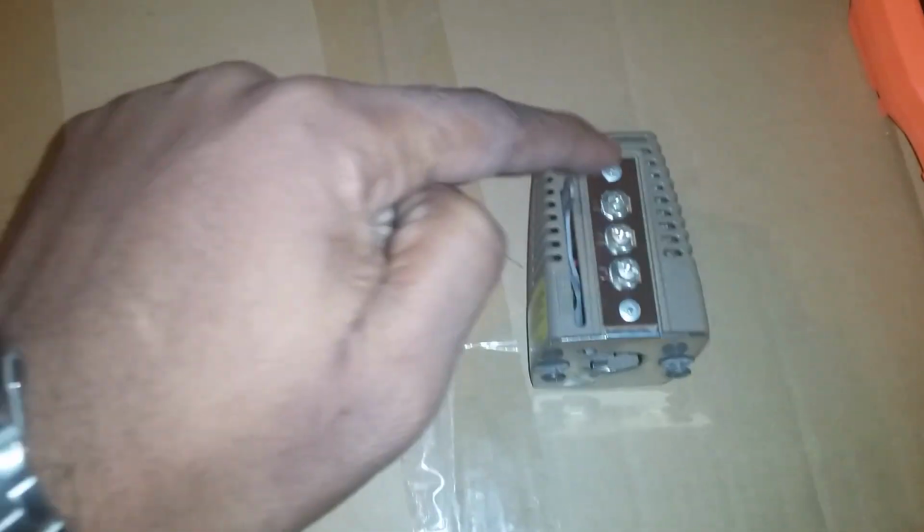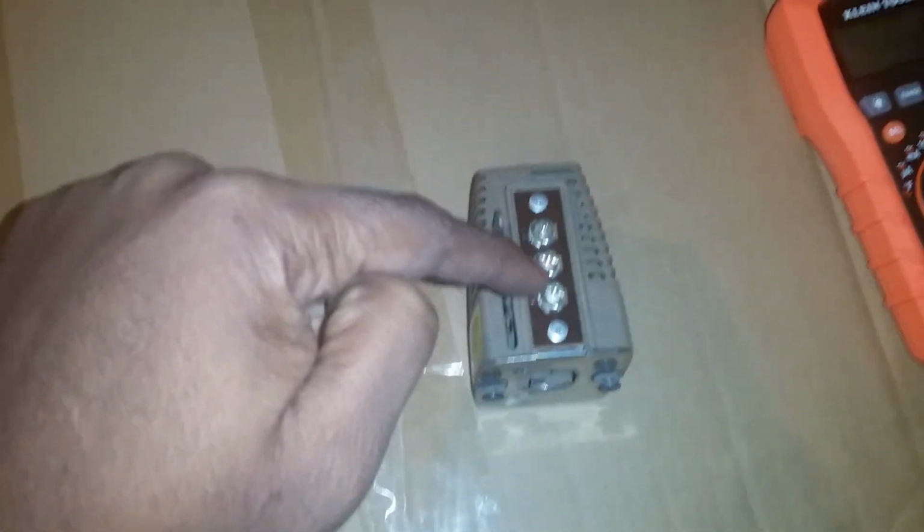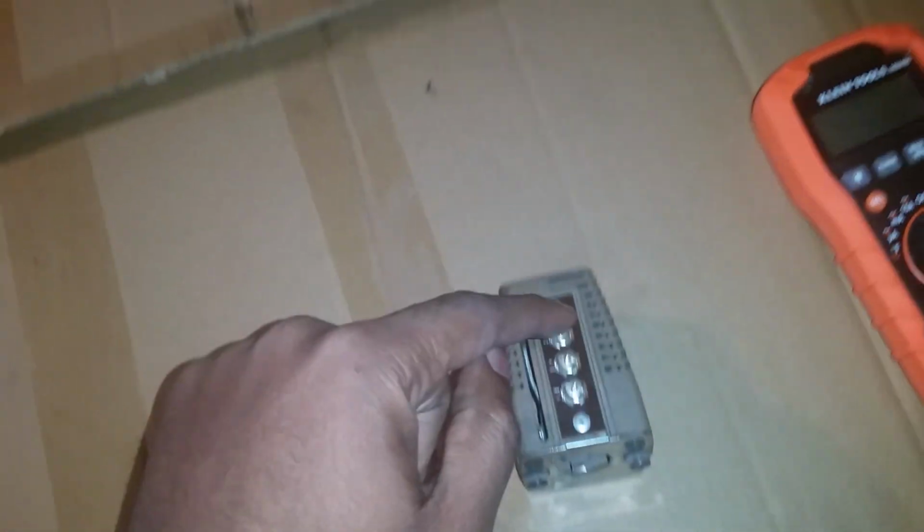Then when the thermostat called for heat, I checked the zone valve. I got 24 volts on 1 and 3, and then after maybe a minute and a half to 2 minutes, it takes that long for the valve to open, it switched to 1 and 2. So, like I said, the relay gets the message back that the valve is open, and then it fires off and turns on the boiler.